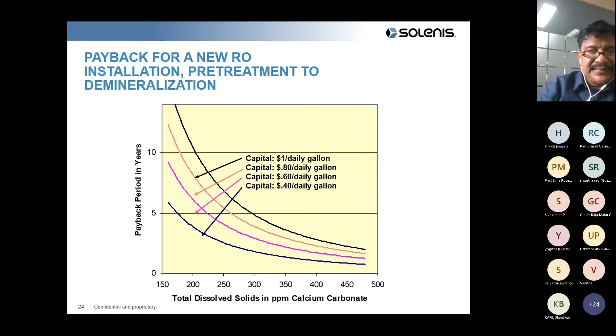I will quickly go into the RO plant, which is a very important system for recycling the plant. This is a very simplified RO process. As I've already discussed with you, you're already an expert on how to do the pre-treatment, because it is very important that the water before it enters a reverse osmosis plant is free of suspended solids. You should ensure there is no organics present, and you should not have any residual chlorine present.